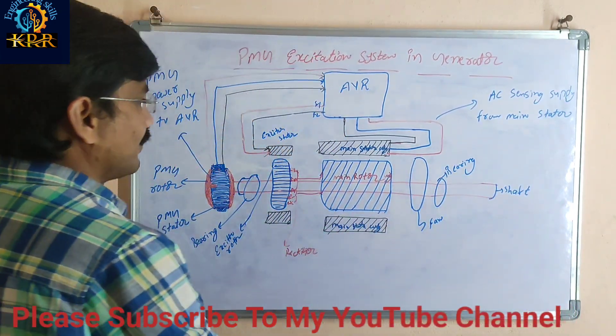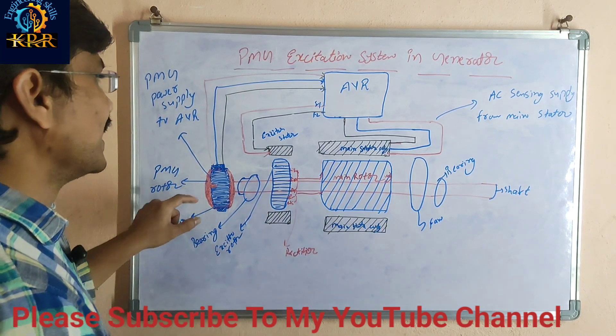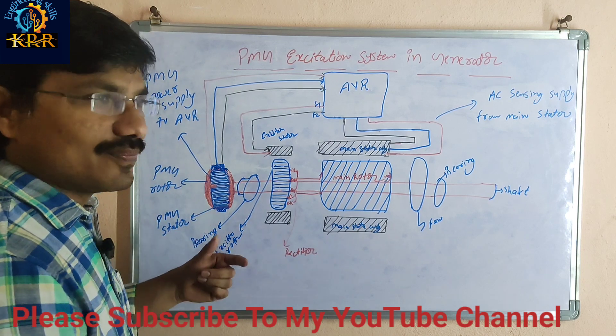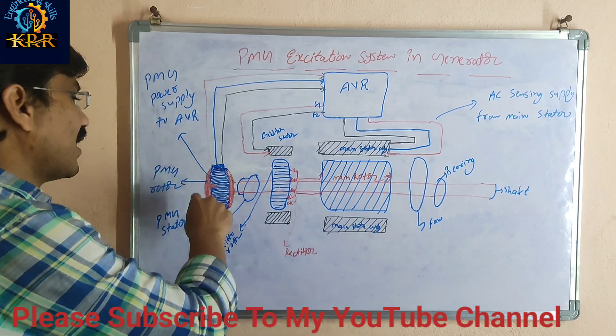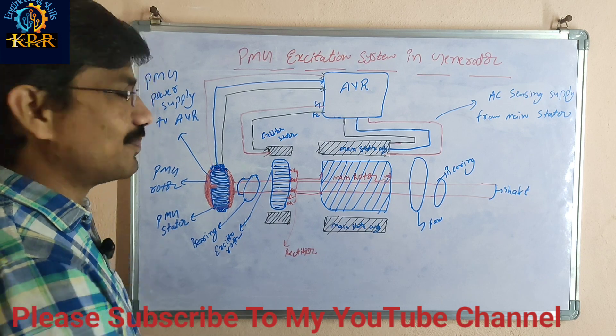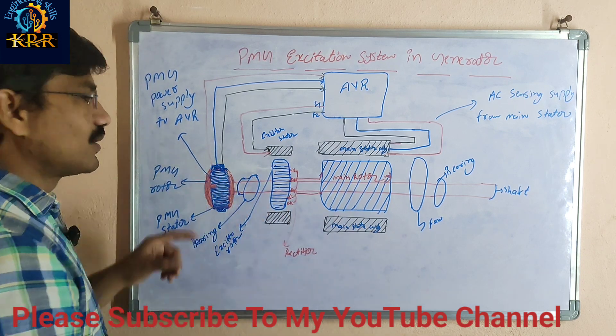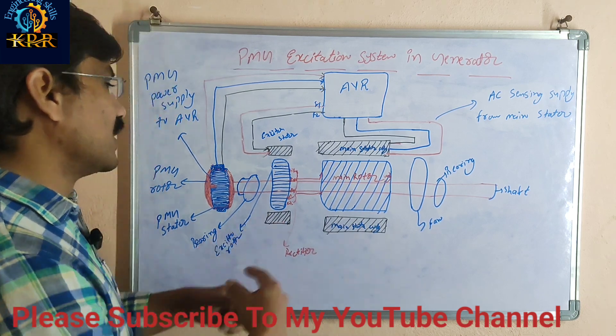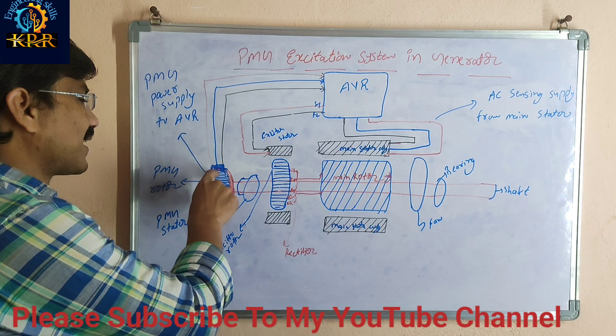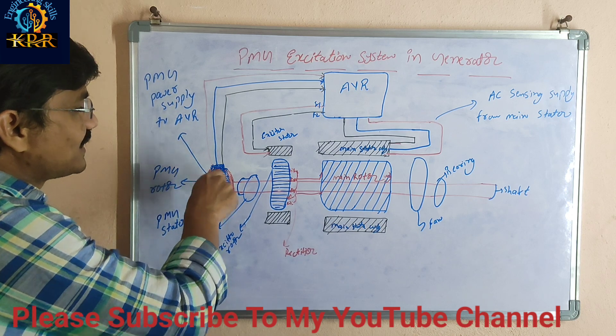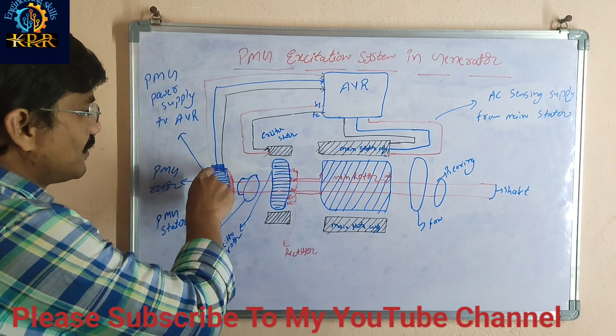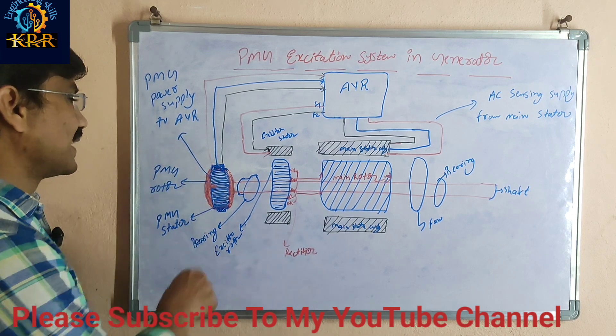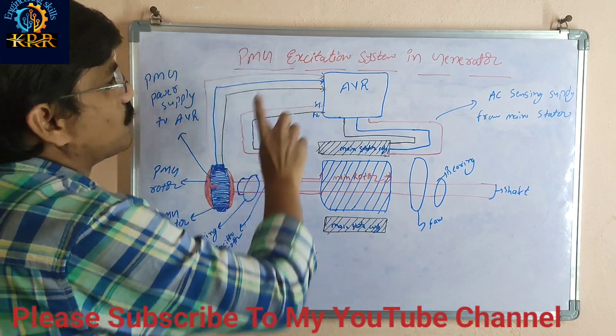As the shaft is rotating, in the PMG the stator winding and rotor permanent magnet are present. The shaft is connected to the rotor — when the rotor rotates, the permanent magnet rotates. The flux is rotating and cuts through the stator winding, so power is generated in this stator.